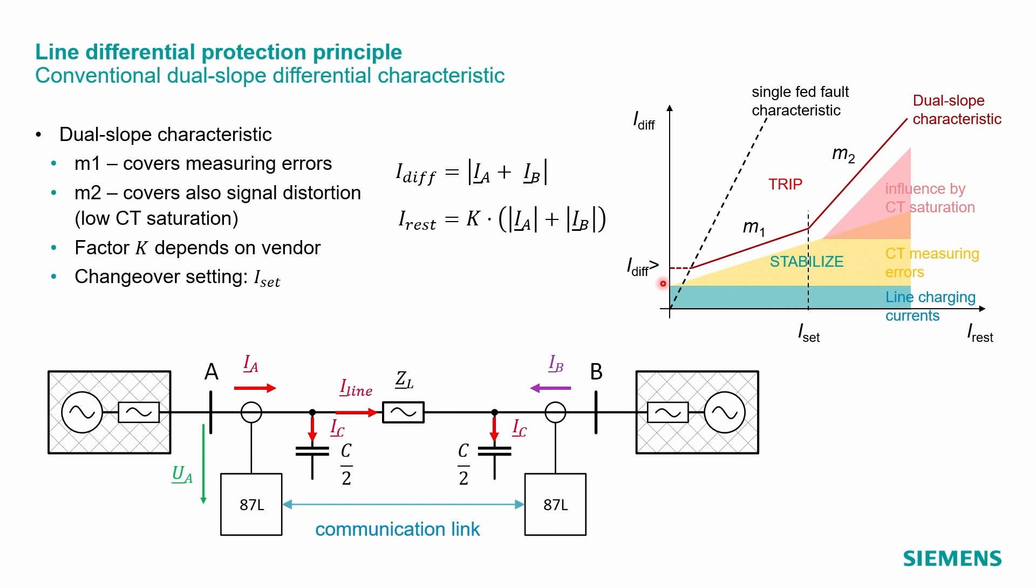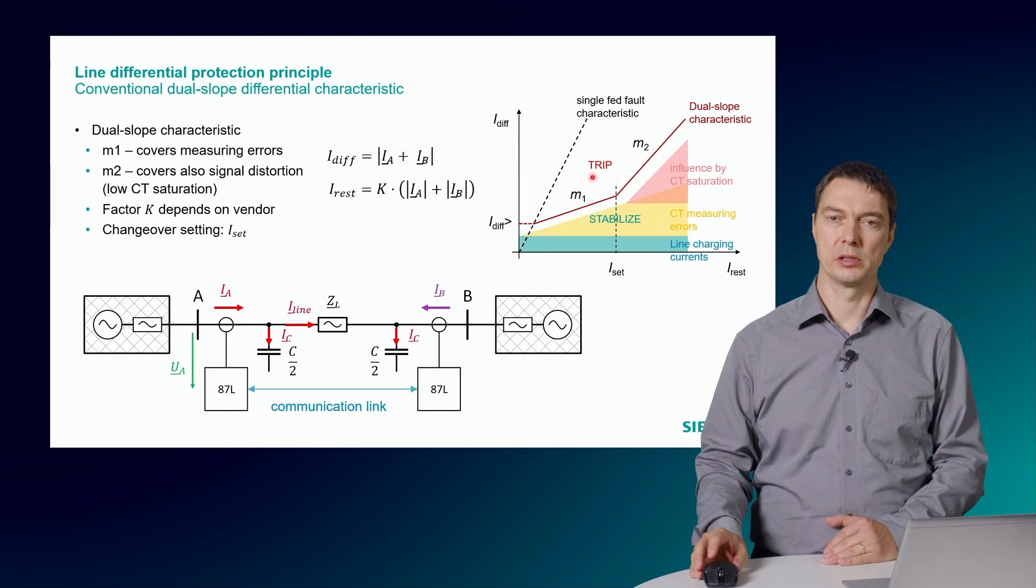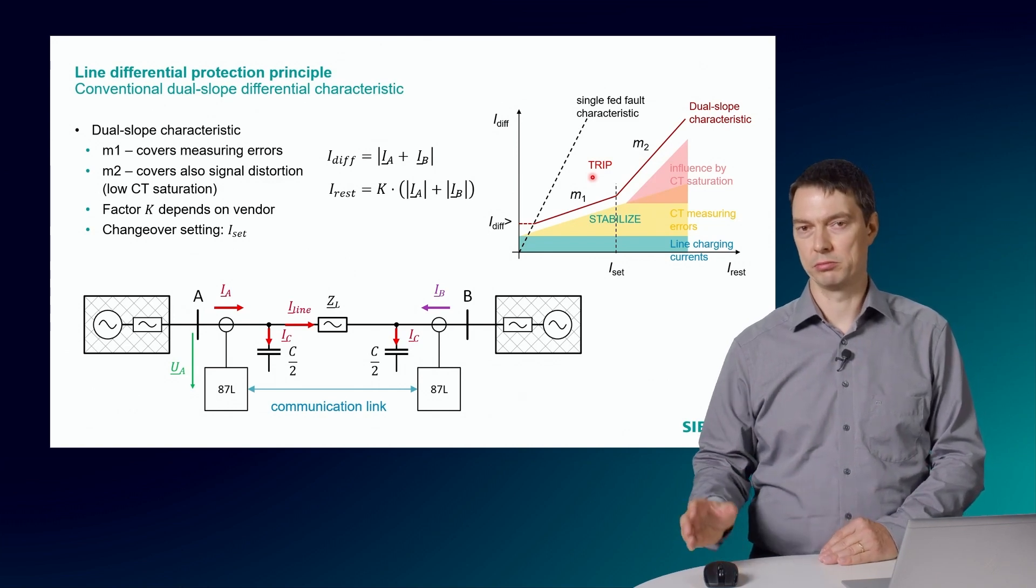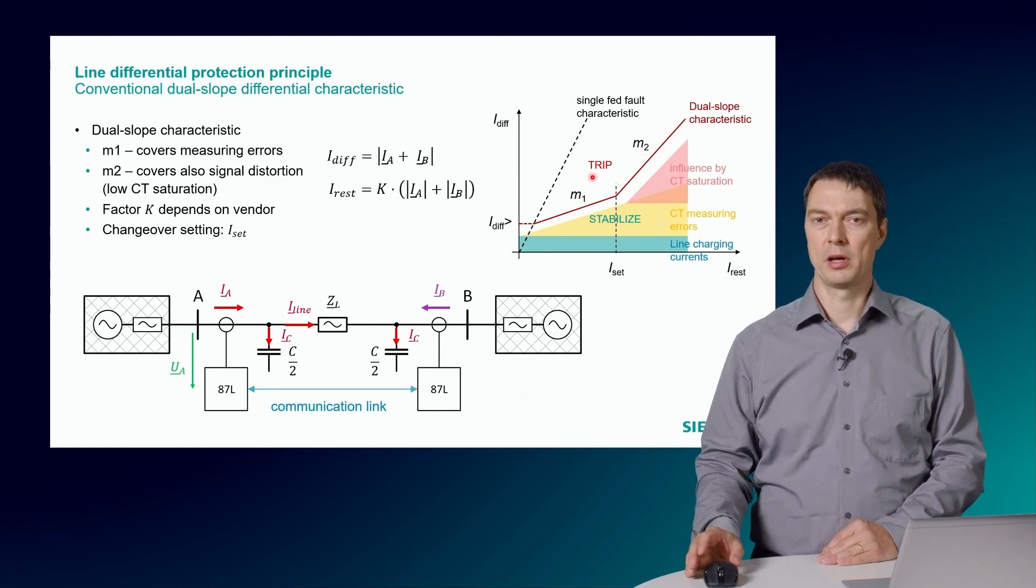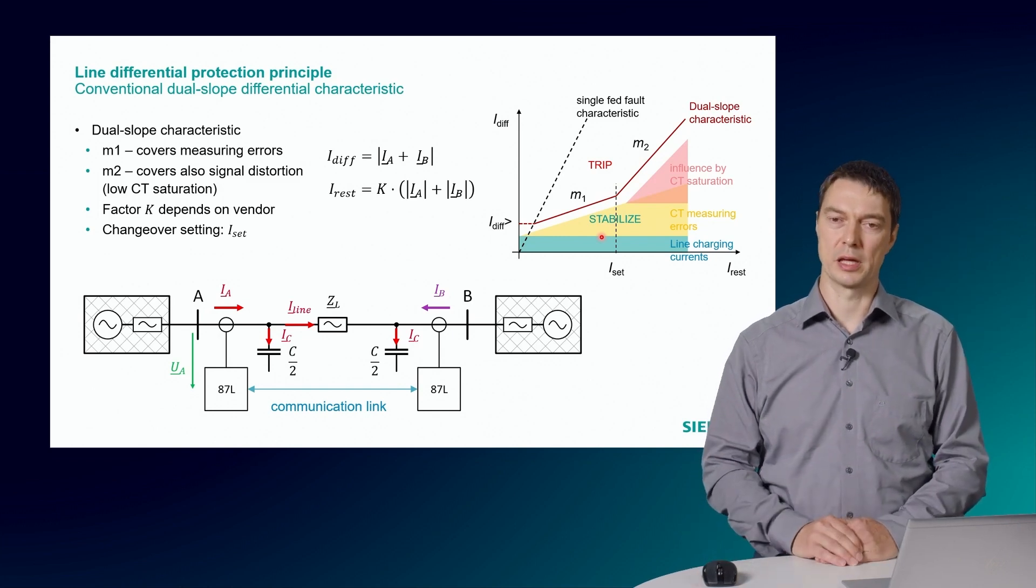The restraining current is calculated as the sum of the absolute current value scaled by a vendor-specific scalar value K. For example, K equals one-half is a typical value. A differential current seen above the characteristic will trip the circuit breaker. And below the characteristic the relay will stabilize and be stable.